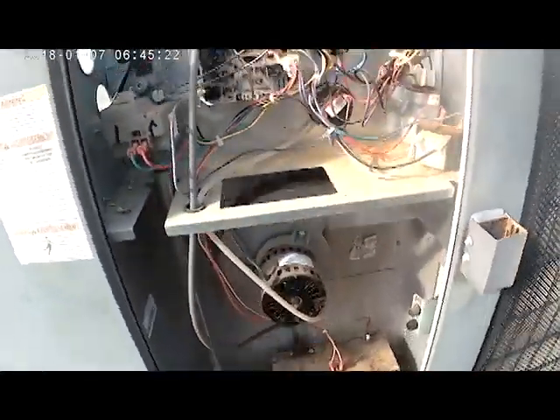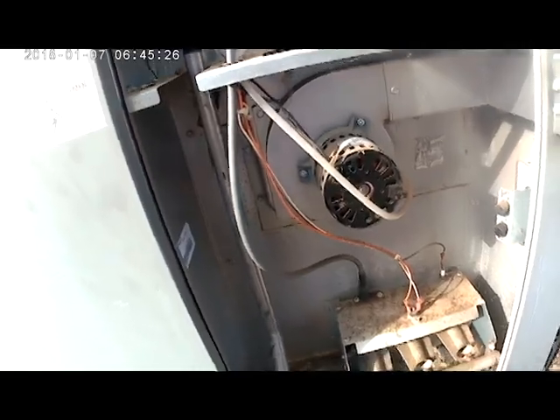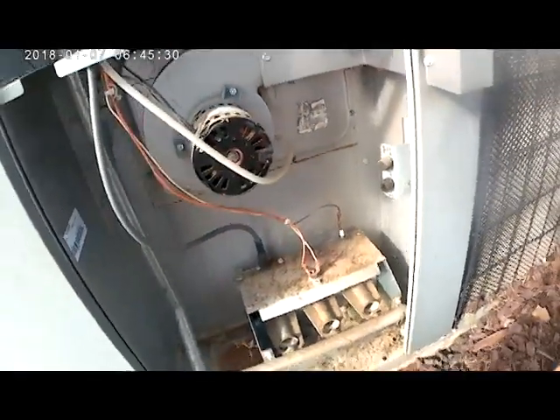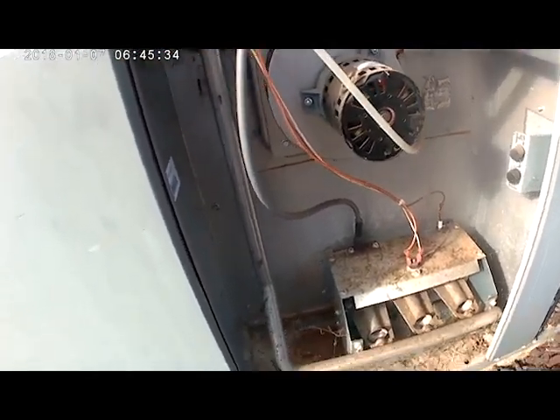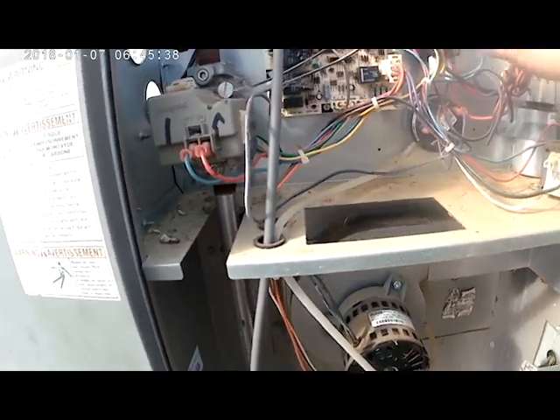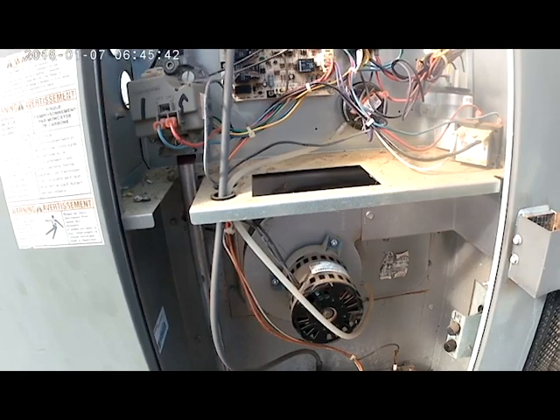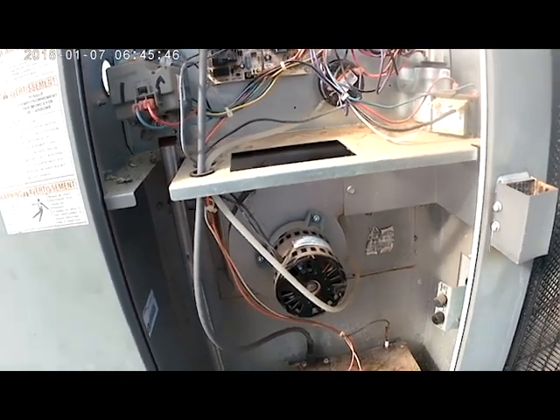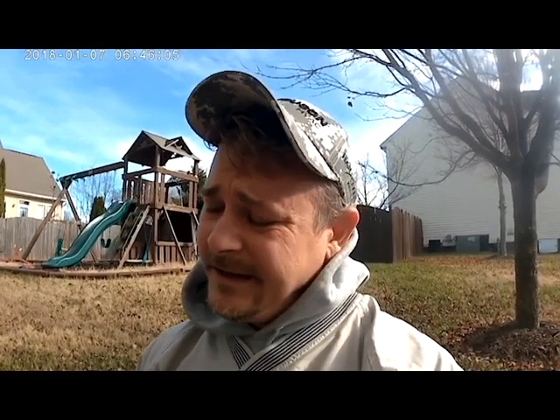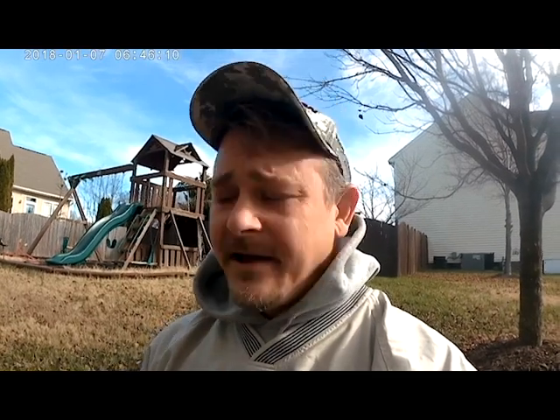Okay, we got the gas valve and the gas pipe loose away from the gas valve. Now we need to see what else needs to come off. I know there's two screws here on the bottom that are probably going to come out. So I'm going to start removing screws until it looks like we can pull this heat exchanger out and figure out how it comes out of here. It shouldn't be too hard, but that's the thing about doing a heat exchanger - you've got to find all the screws that hold it in. Once you find those, it's pretty much easy from that point. Since this is a heat exchanger I've never done, I've got to hunt down all the screws holding it in and see where they are. I'll see you back when I get some of these screws out, and I'll show you where they are as we pull this heat exchanger out.